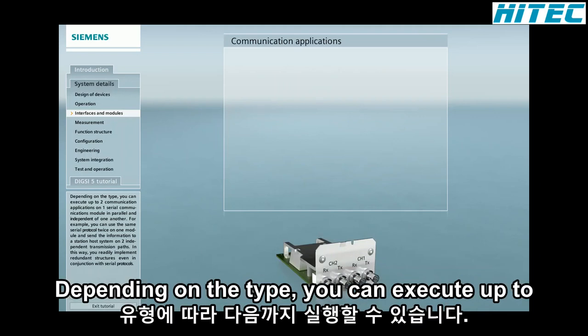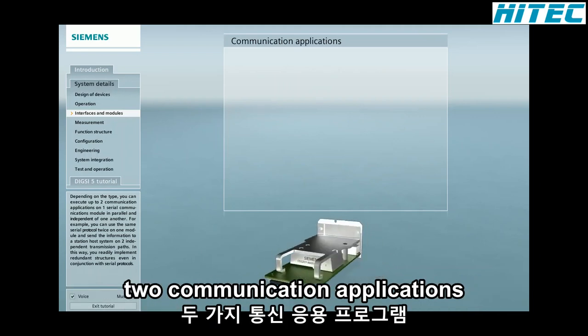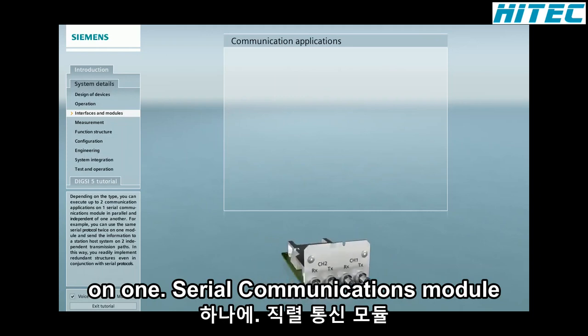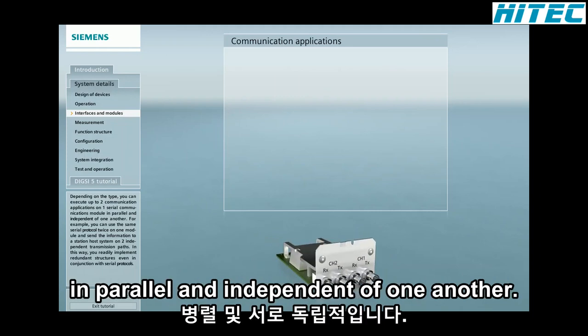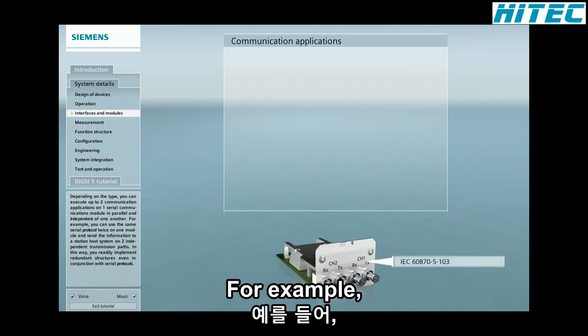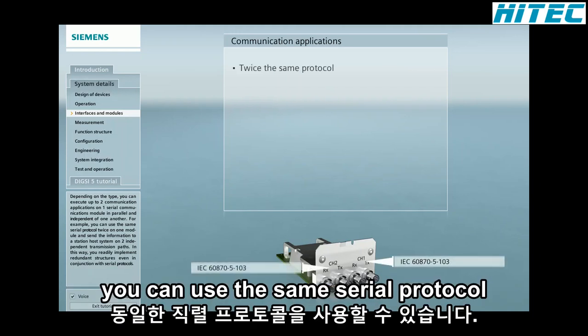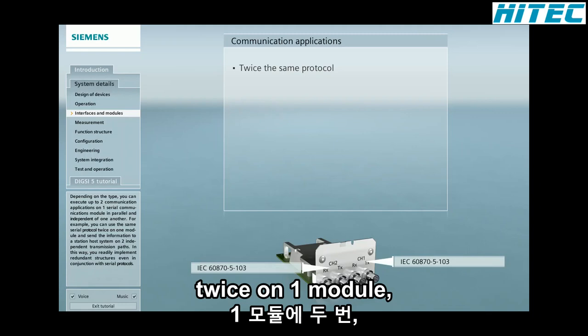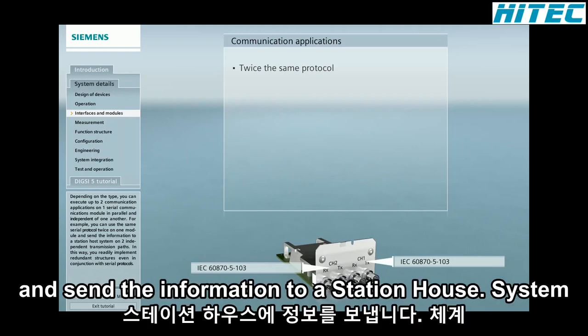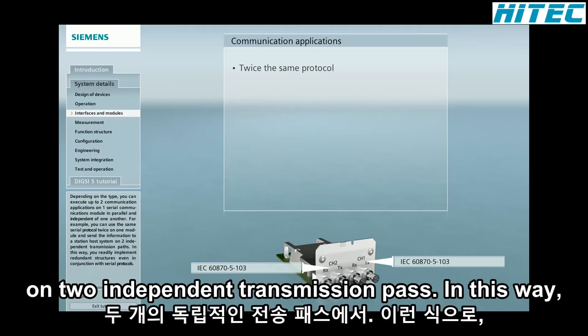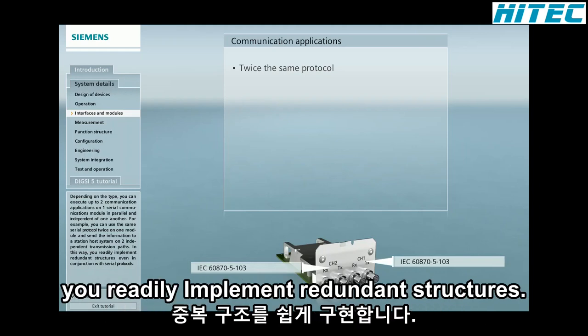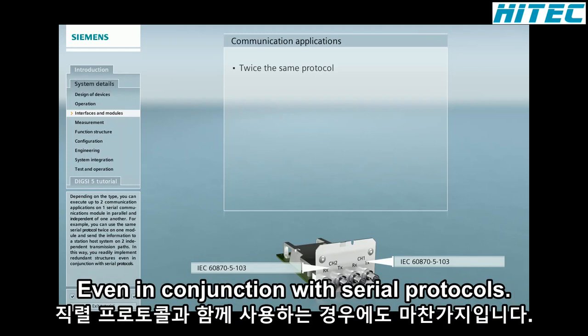Depending on the type, you can execute up to 2 communication applications on one serial communications module in parallel and independent of one another. For example, you can use the same serial protocol twice on one module and send the information to a station host system on 2 independent transmission paths. In this way, you readily implement redundant structures even in conjunction with serial protocols.